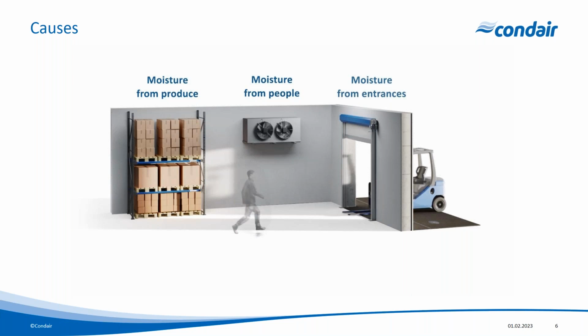So it's critical to know how many doorways we've got, what is the temperature difference between those doorways, and also what are we doing to mitigate that air change rate. Have we got strip curtains? Have we got polar strip curtains? Have we got air curtains? Have we got fast-acting doors? Have we got some way of mitigating that open door? Have we got a robust regime that we're educating our staff to have to keep the doors closed? So moisture is going to be coming in through that doorway or even an open conveyor hatch at a rate relative to the difference in vapor pressure between the outside and inside.